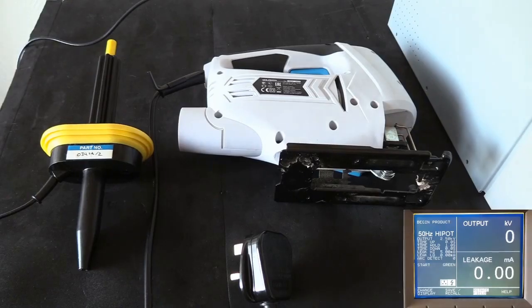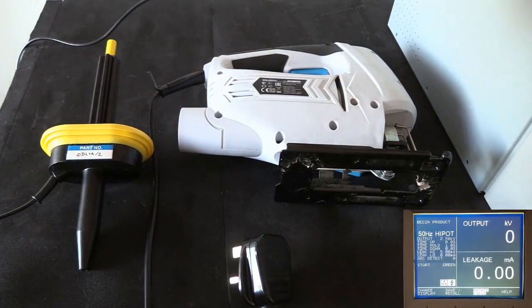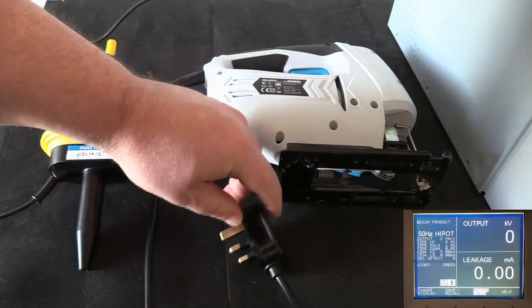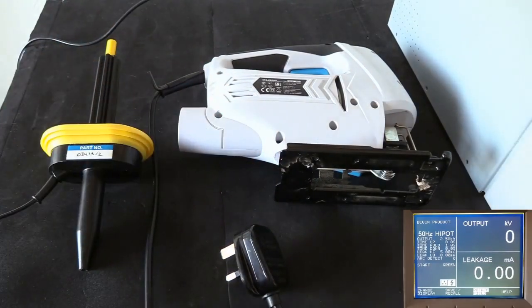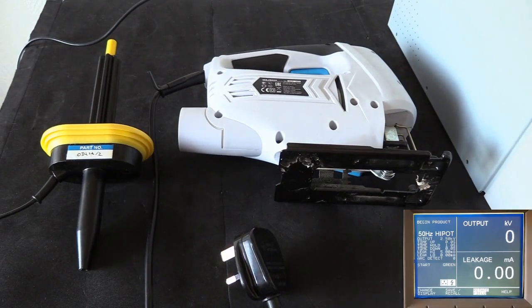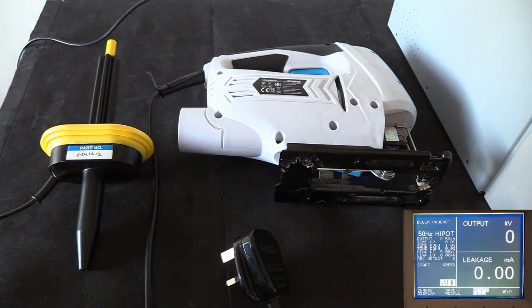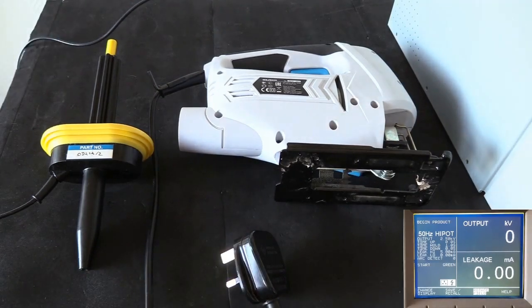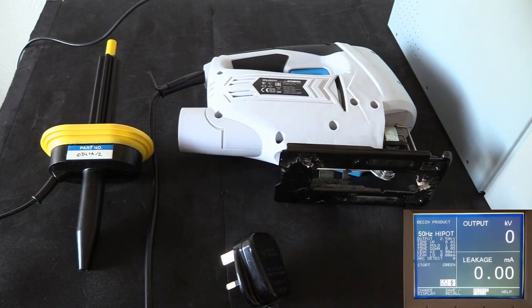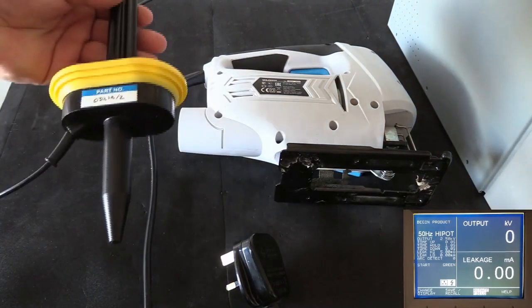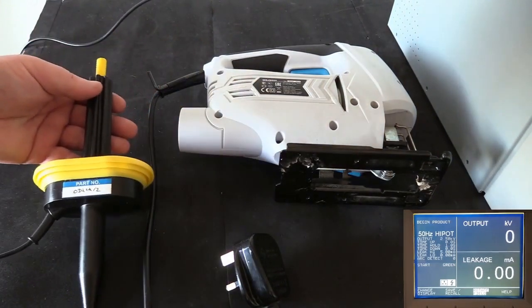So now we're going to be testing a double insulated or class 2 product. For this particular product, we're going to be testing a jigsaw. The jigsaw is connected to the mains via a supply plug. So we're going to be using our output connection. Now, because this is double insulated, there is no earth connection to the device, so we have to supply an external connection to read any fault leakage current back into the device. And for this particular example, we're going to be using our return probe.